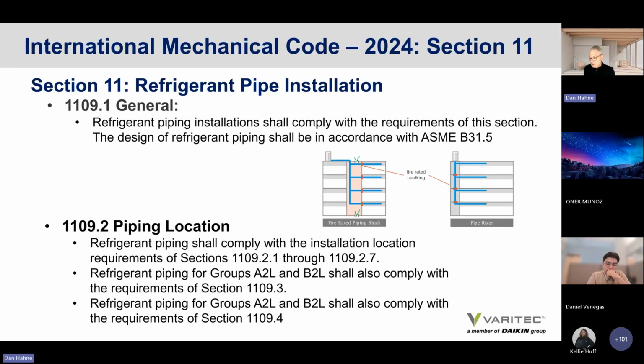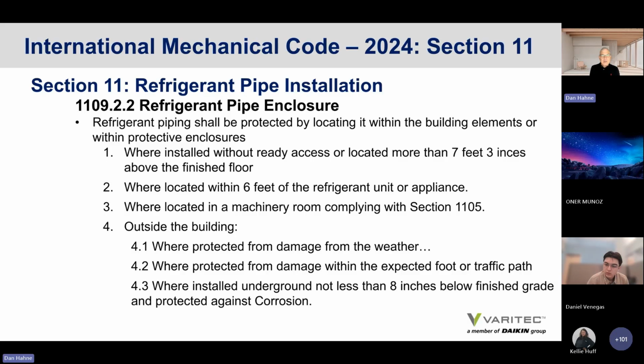And I'm going to go through this quickly as we're rapidly running out of time. I used IMC 2024 as a reference. It gives language on refrigerant piping installations that need to comply with ASME B31.5. It offers piping location directions regarding compliance and which sections are to be applied. It looks at refrigerant pipe enclosures. Refrigerant piping shall be protected by locating it within the building elements or protective enclosures. It gives direction on where that piping is to be located, whether indoors or outdoors.